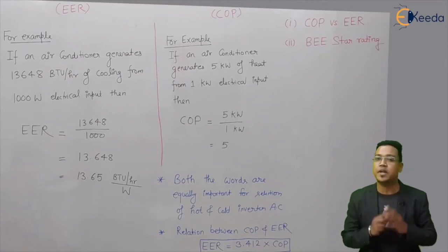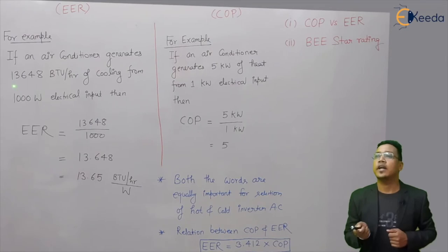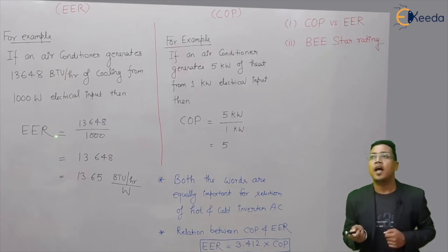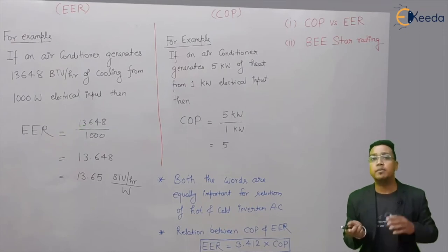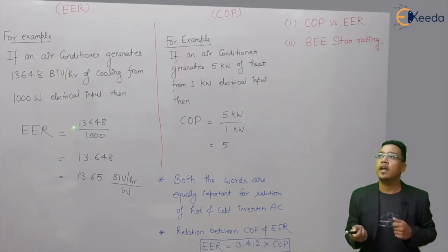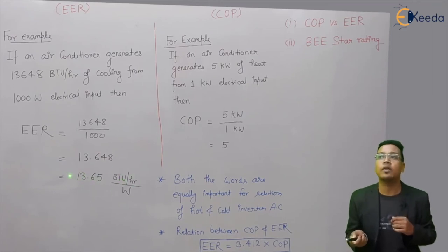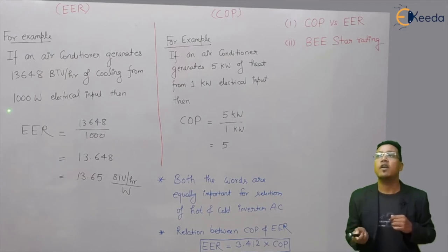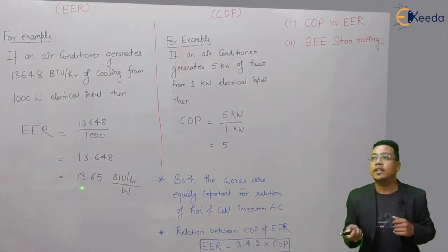Let us look at EER and COP with the help of one example. For EER: if an air conditioner generates 13,648 BTU per hour of cooling from 1000 watt electrical input, then EER equals 13,648 divided by 1000, which gives 13.65 BTU per hour per watt.